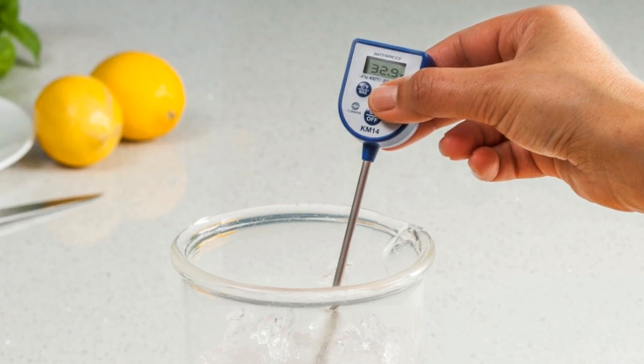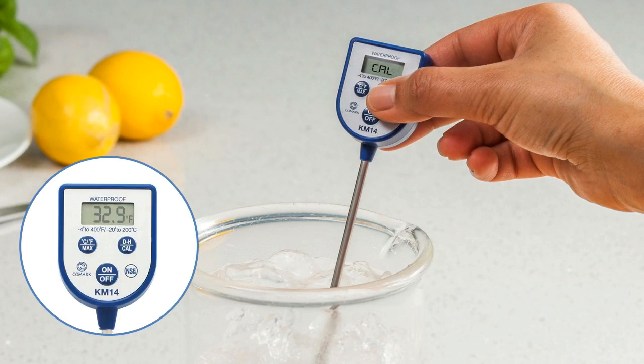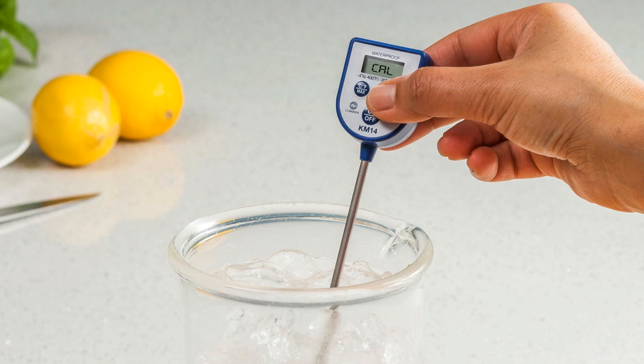To begin calibrating your pocket digital thermometer, you should press and hold the cal button for 8 seconds. On devices that don't have a cal button, the DH or data hold button is usually used instead. The digital display should show the cal message for around 2 seconds, after which the recalibration to 0 degrees Celsius or 32 degrees Fahrenheit will have been completed.